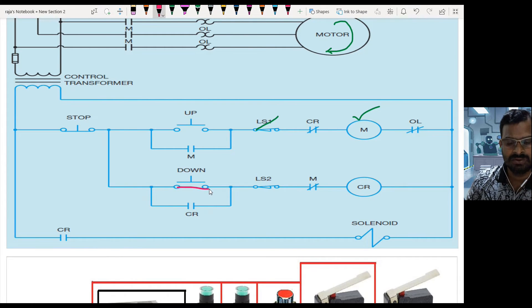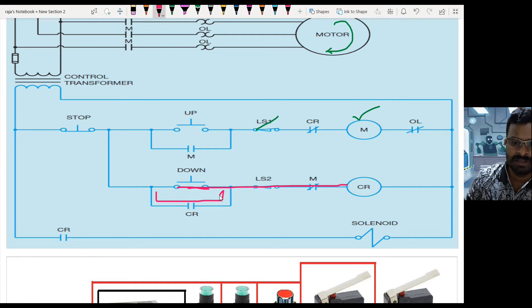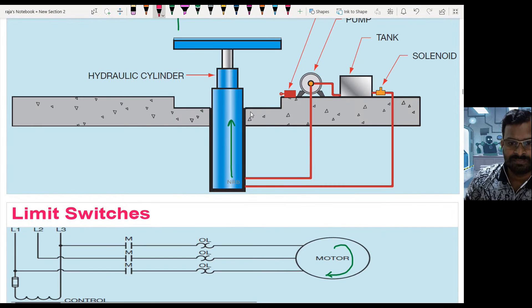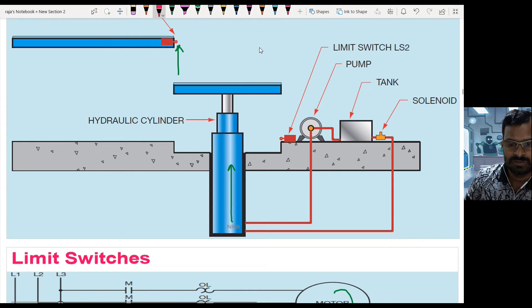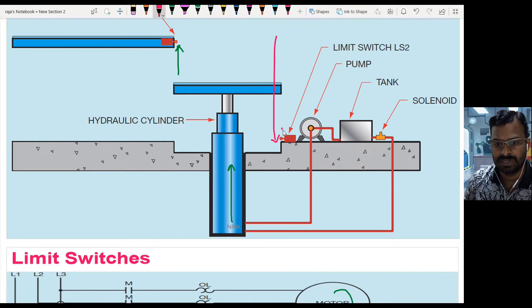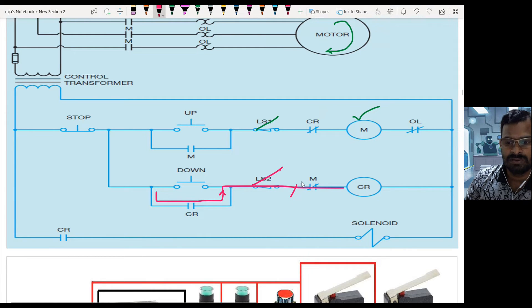When the operator wants to bring it down, they operate the down switch. When pressed, current flows to the control relay. Once the control relay is energized, latching takes place and current flows in the down direction. When the cylinder comes down and reaches the bottom position, LS2 opens the circuit and the current flow stops.